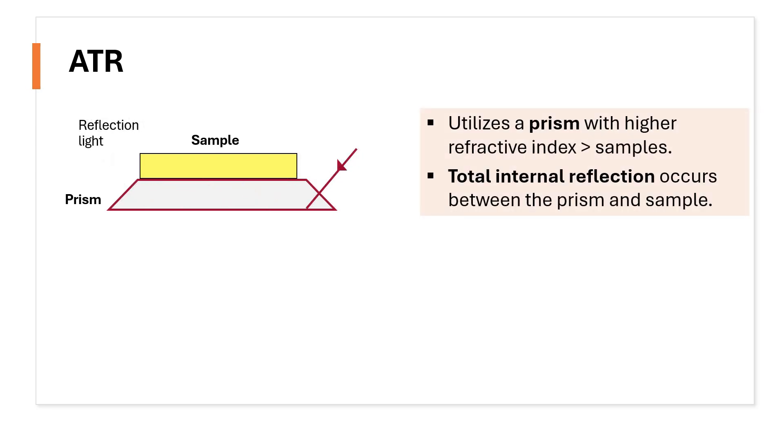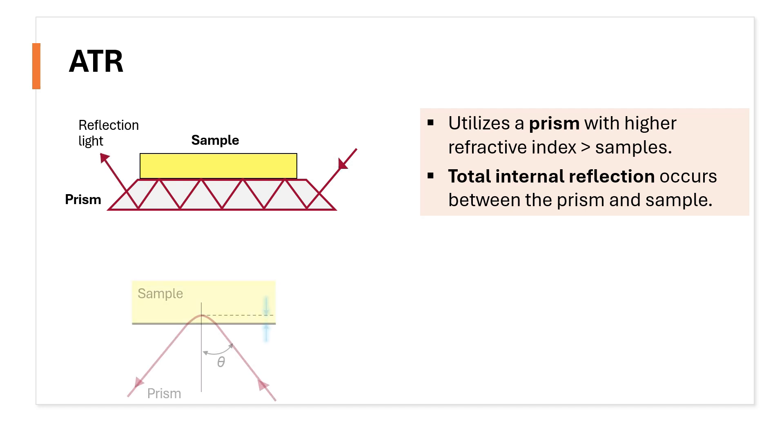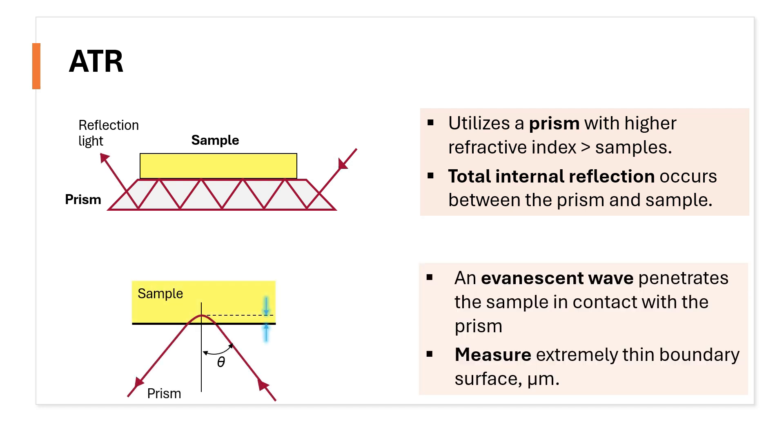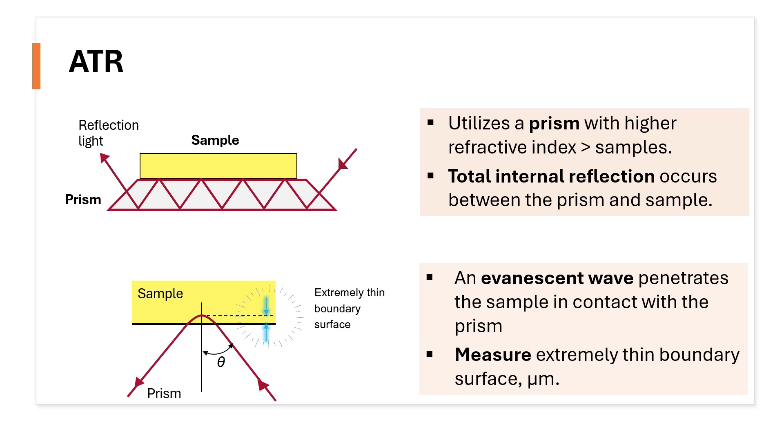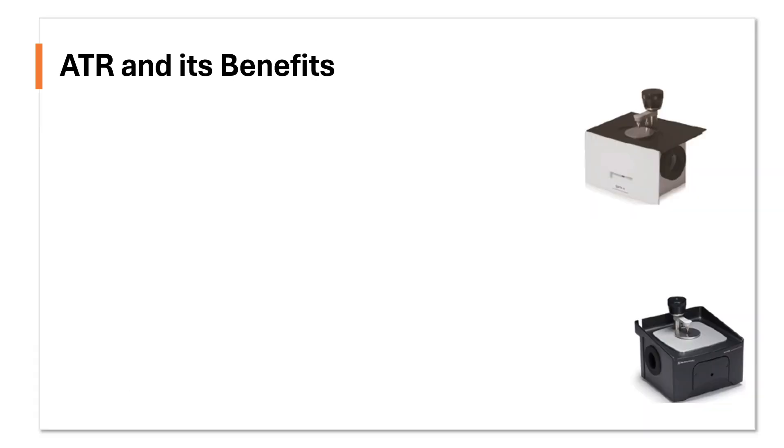It starts by utilizing a prism with higher refractive index than samples, example diamond. Then a total internal reflection occurs between the prism and sample. An evanescent wave then penetrates the sample that's in contact with the prism. The instrument then measures this extremely thin boundary surface where the sample comes in contact with the prism.